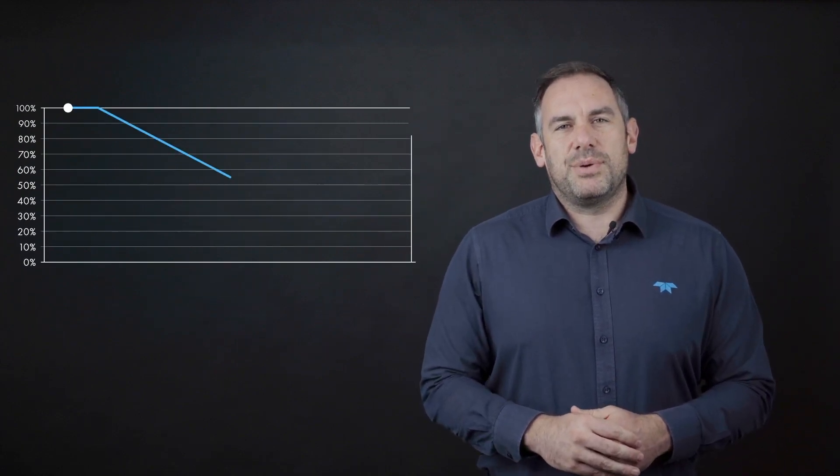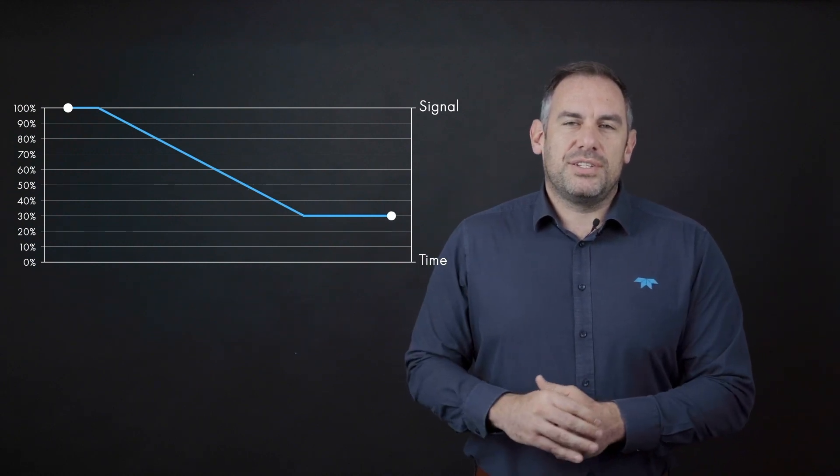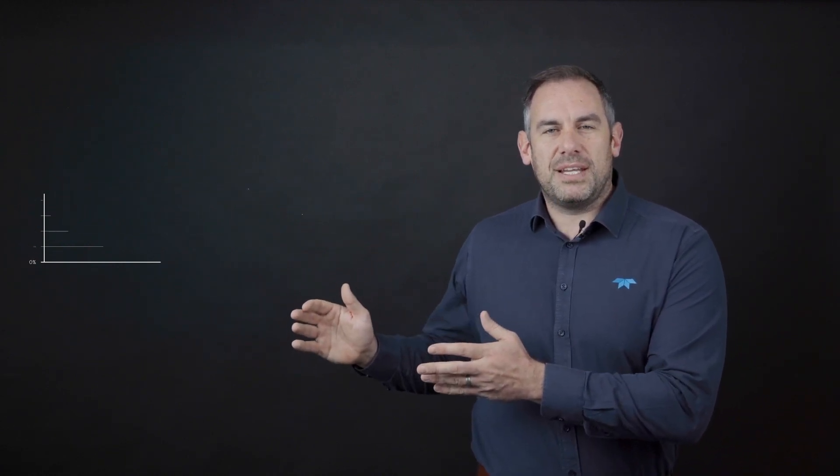In theory, if the contamination stays linear between the date of installation and the date of the early dirty optics warning, you have about 50% of that time to schedule in the cleaning of the lens before the device drops to the 70% absorption and goes into a genuine fault condition.